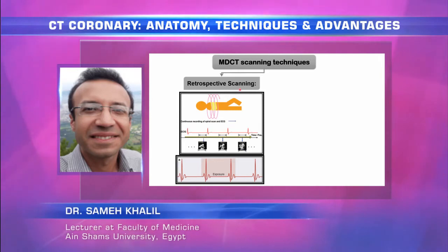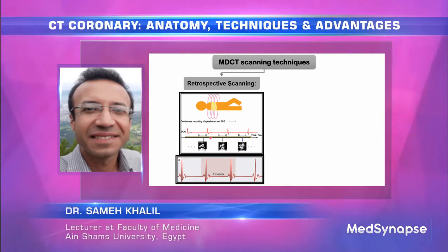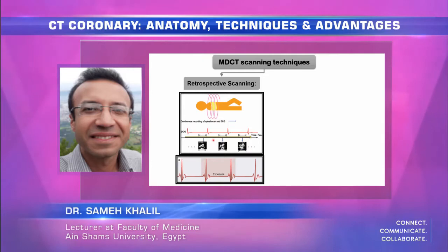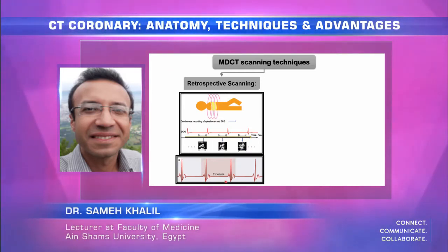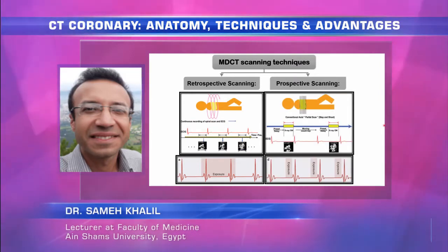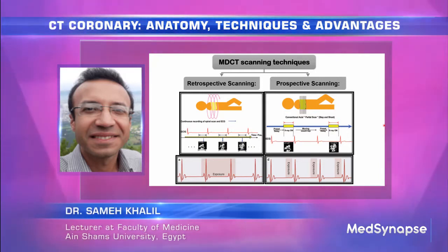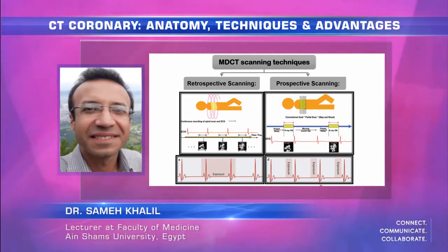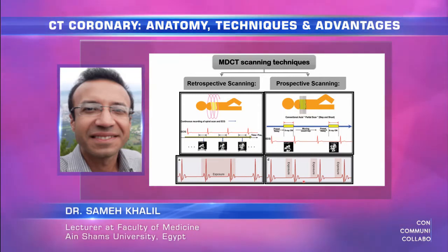Our technique includes the retrospective approach, in which X-ray is on throughout the entire cardiac cycle — both systole and diastole — giving us images across all cardiac phases but delivering more radiation dose. We also have the prospective approach, in which X-ray is delivered in a specific phase: mostly diastole for coronary artery assessment, and systole for congenital heart disease assessment.